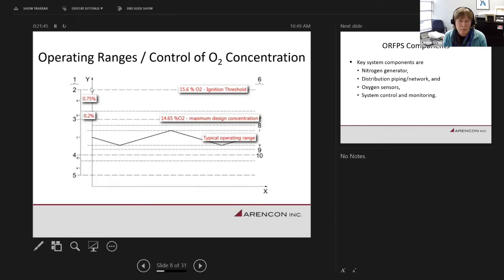So X is essentially looking at time. I'm not sure if this shows my cursor as I'm talking here. I don't think so. But the X-axis represents time, and the Y-axis represents the oxygen concentration. The line 2, or the dash, is essentially your ignition threshold. That's determined by testing. Oxygen concentrations above that level would sustain fire. Oxygen concentrations below that level do not sustain fire.